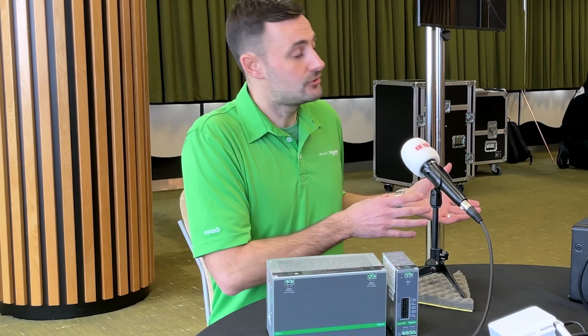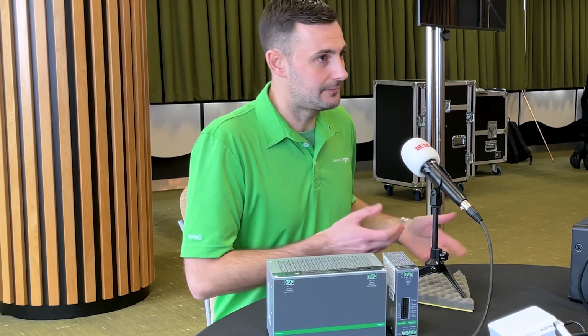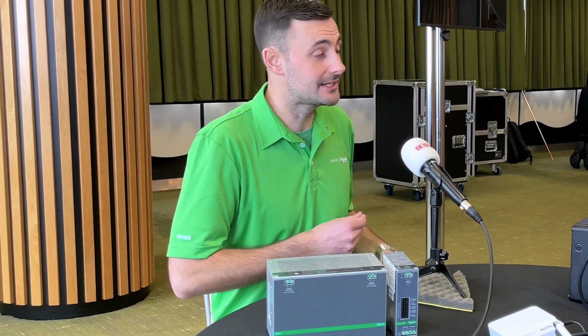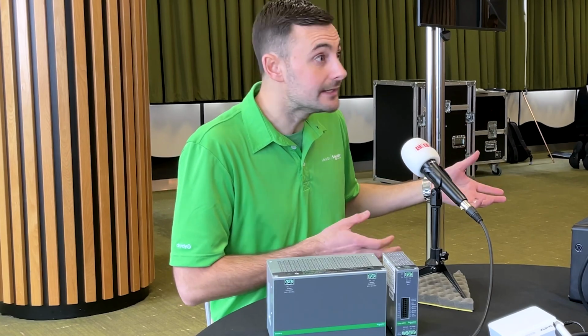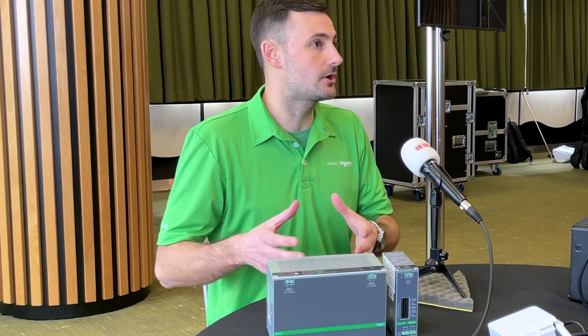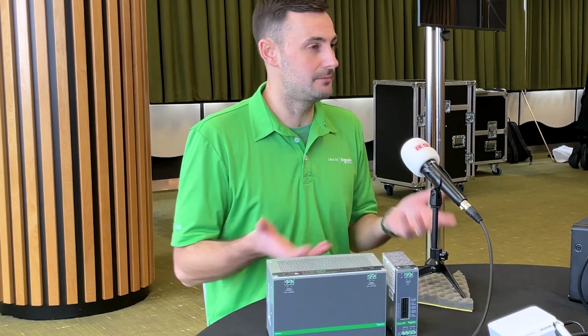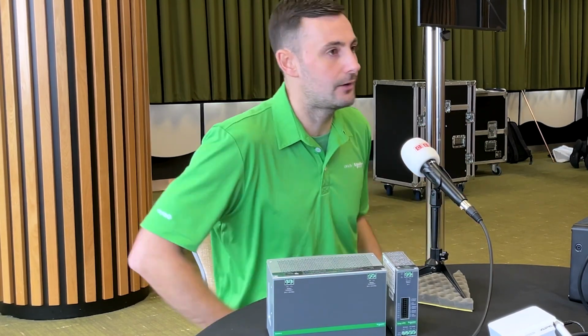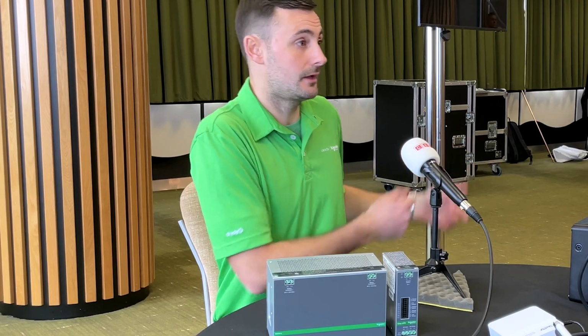The thing is, with those generators, they don't kick in automatically - it can take several seconds, up to 30 seconds, depending on whether it needs to be started automatically or manually. So the idea is the battery inside a UPS system gives you immediate power, allowing you to then transition to a longer-term generator.